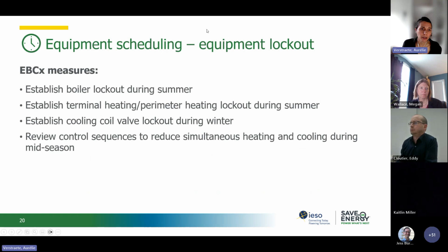For equipment lockouts, we can establish a boiler lockout during summer. You can authorize a boiler to start only under a certain outdoor air temperature. You can also have lockout on terminal heating, perimeter heating during summer, and cooling coil valve during winter. Then you can review control sequences to reduce simultaneous heating and cooling during mid-season.